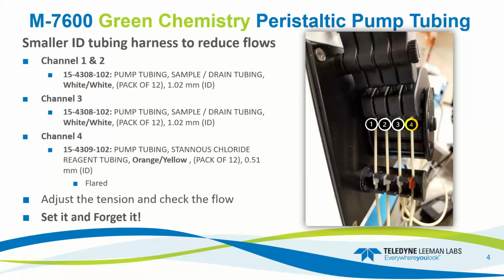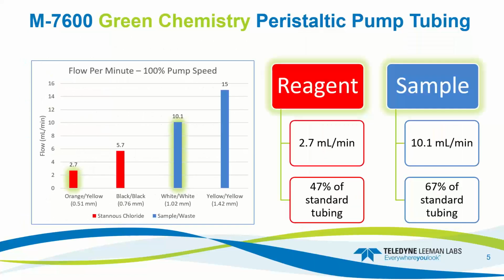And so when you convert to the new tubing, you'll need to adjust the tension on the levers. This process is best described in the user's manual for the instrument. I'm also putting together a YouTube video for this procedure, so keep an eye out for that. But basically, you'll want to twist the screws so there's no tension on the tubing, then slowly increase the tension by turning the knobs. Once you get a jerky back and forth motion through the transfer lines, then you'll do one full 360 turn and lock it down, and that should be just about perfect. So again, consult your manual for that, and remember to set it and forget it. Always change the tubes and not the tension when it's time for maintenance.